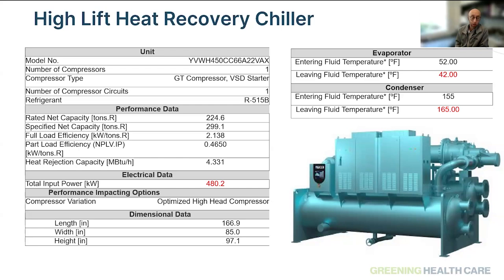There are heat recovery machines out there that use multiple stages of compression, and when you're doing just conventional cooling, and you only need the cooling load, there's no heat rejection, you just want to dump the heat out to a cooling tower, you can have the same efficiencies as a standard centrifugal chiller. If you need to design for a different type of system, where you want to use a positive displacement machine, then yes, you might take a bit of a sacrifice on that standard cooling capacity.